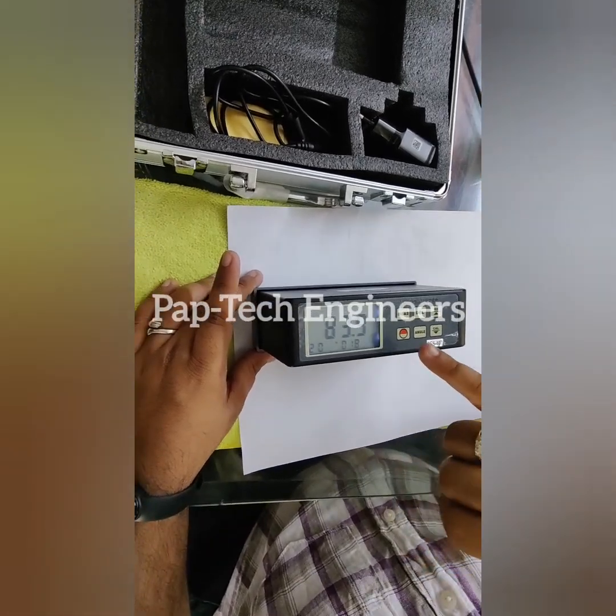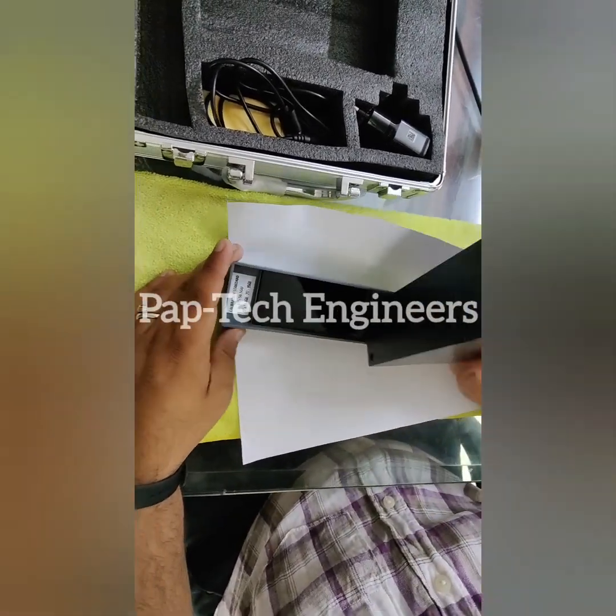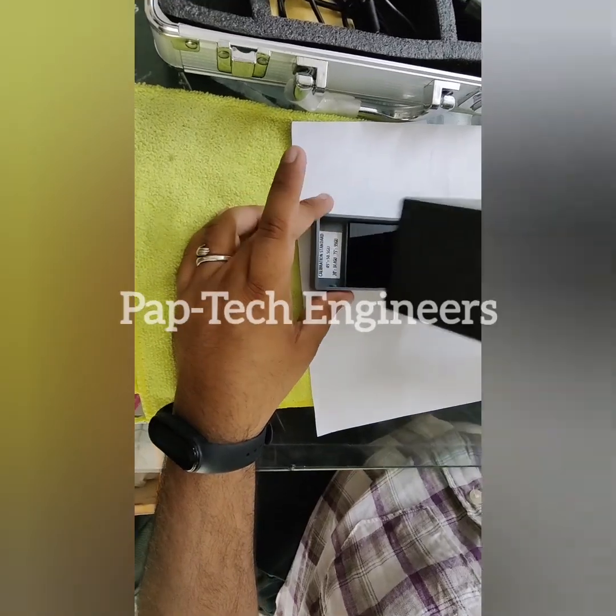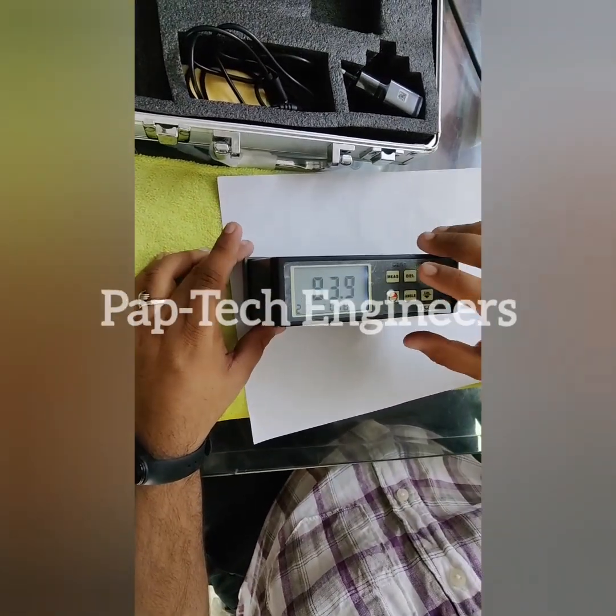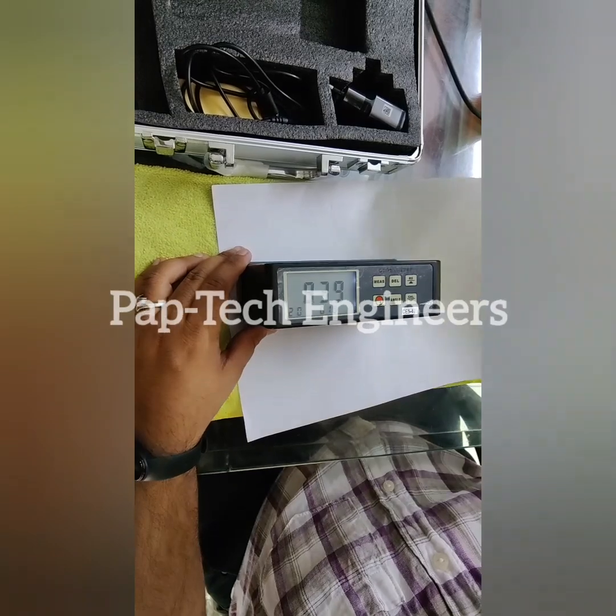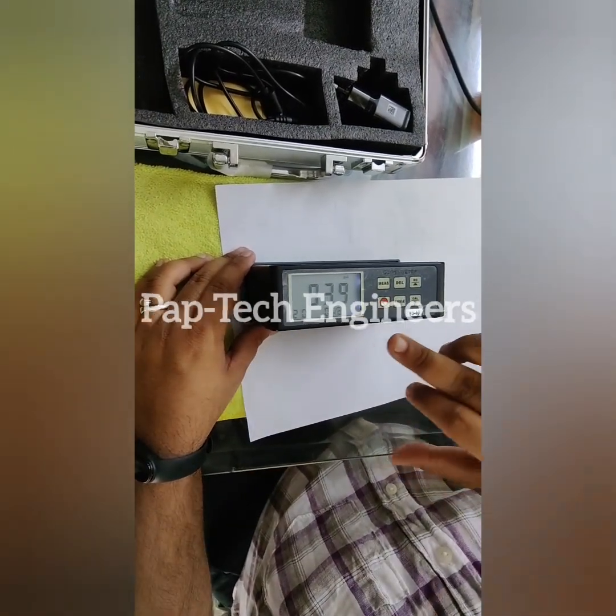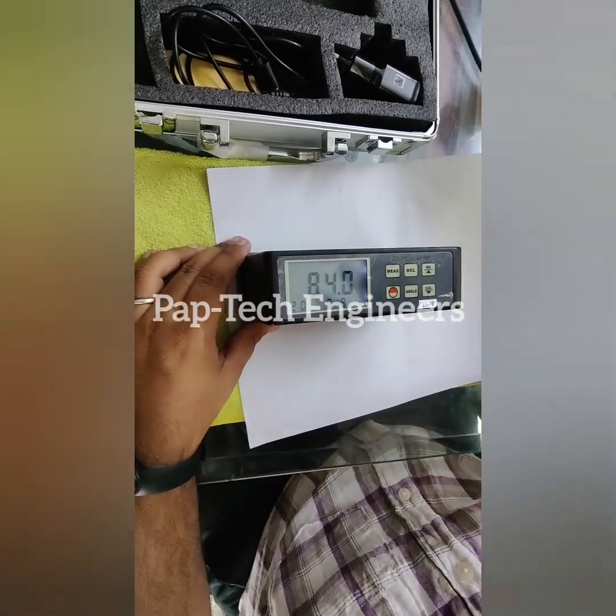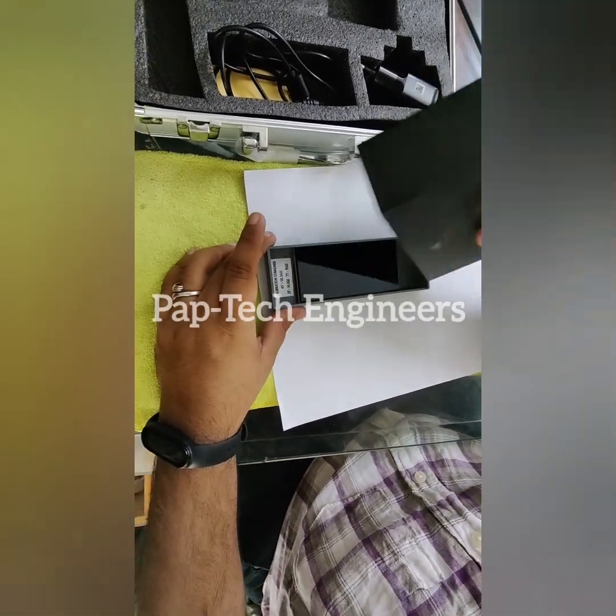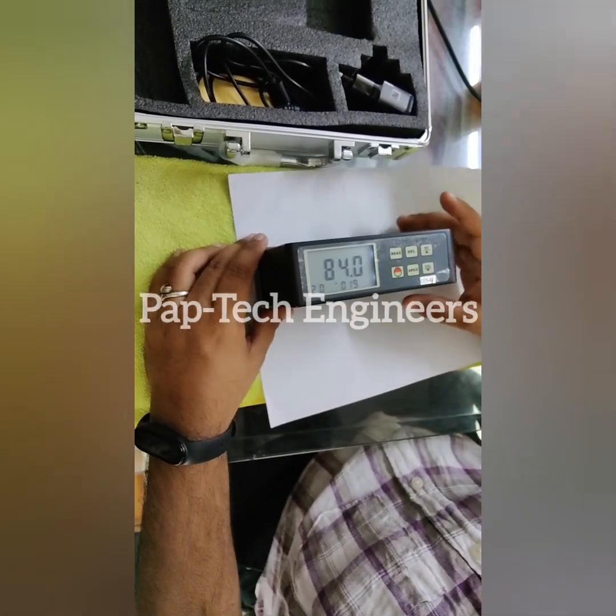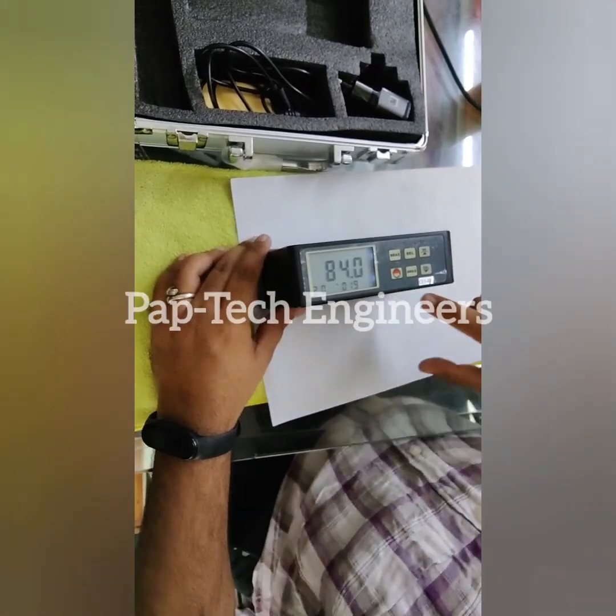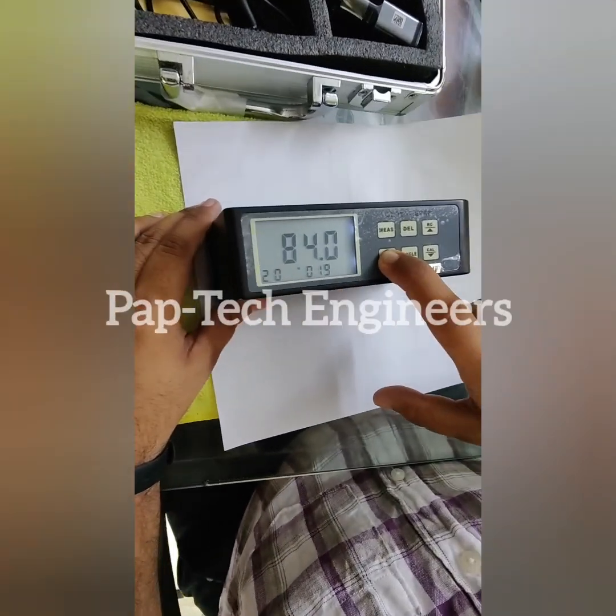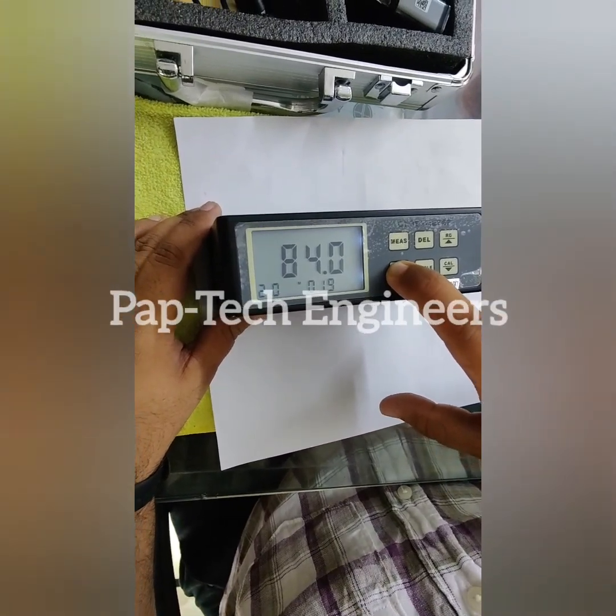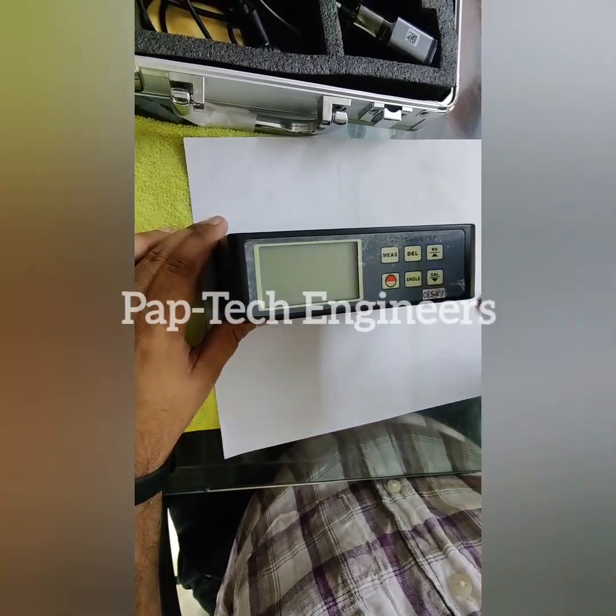Now let's check on the calibrator how much it's coming at 20 degree. As we can see, 83.9 is coming and it should show 84.4. It means the machine is showing the correct value. Okay, because as I said, 1.5 to 2 can be the error. Again we can see the reading is coming 84. So it is completely perfect. The machine is working very fine. And with this button, if you press it long, we can switch off the machine. So this is how we can switch off the machine.